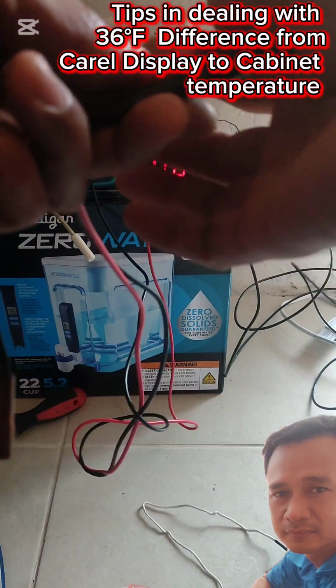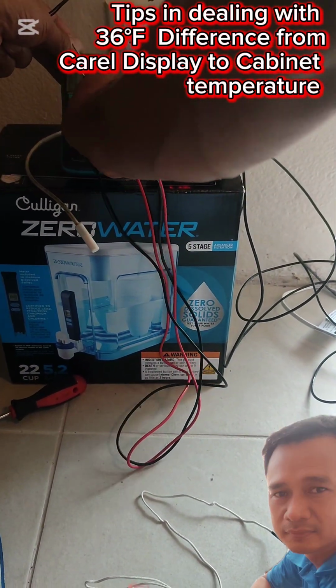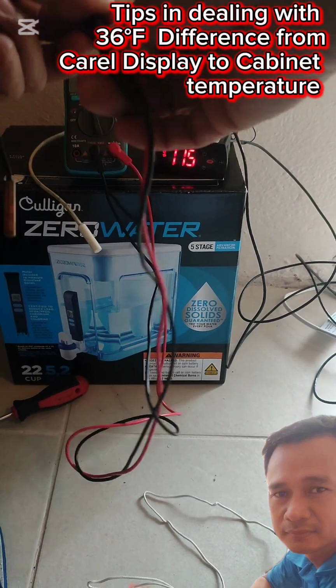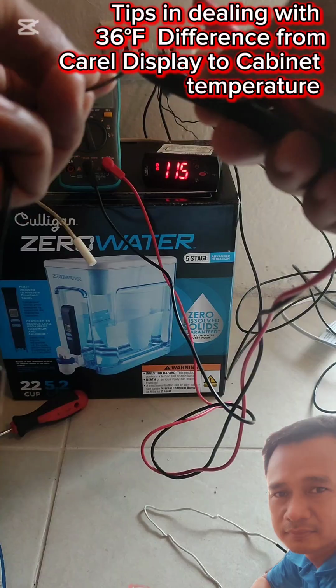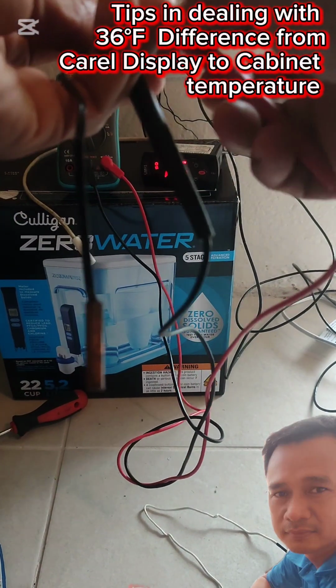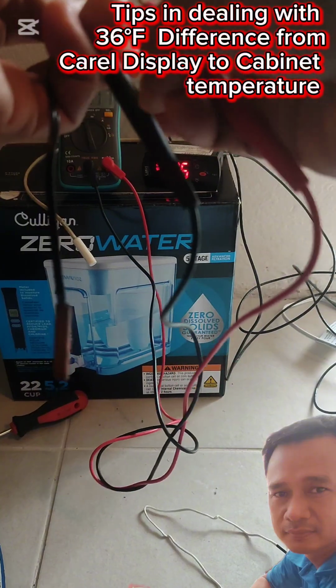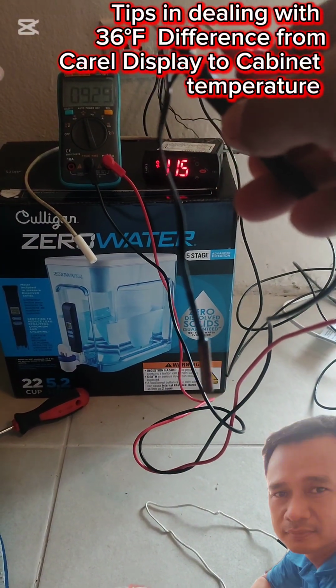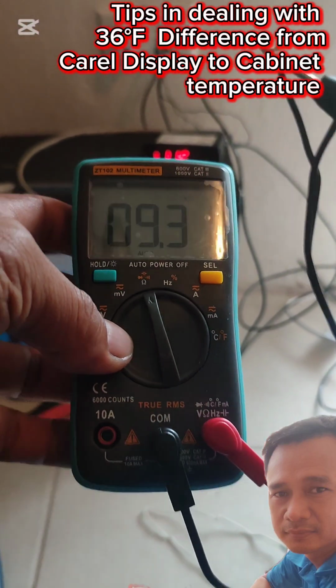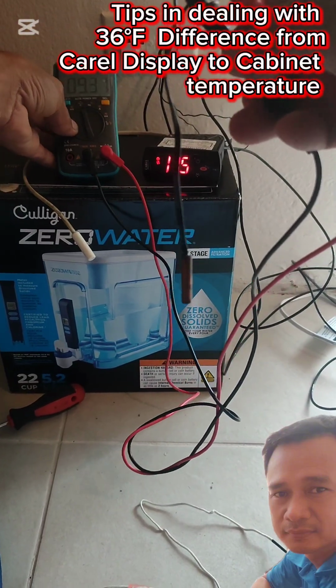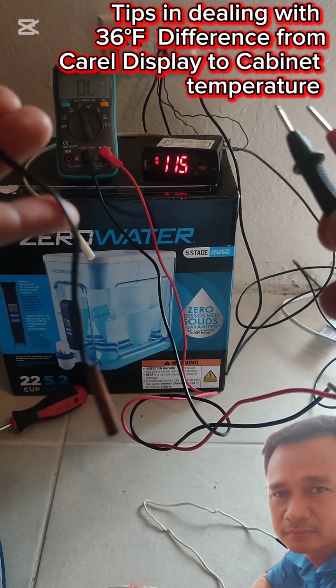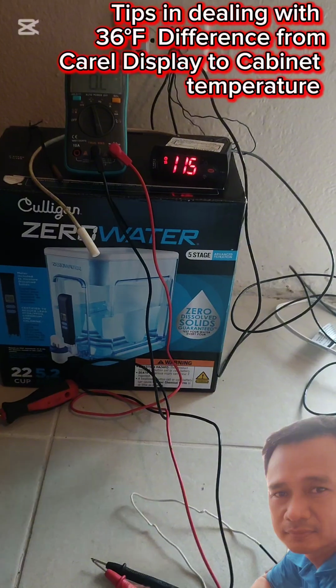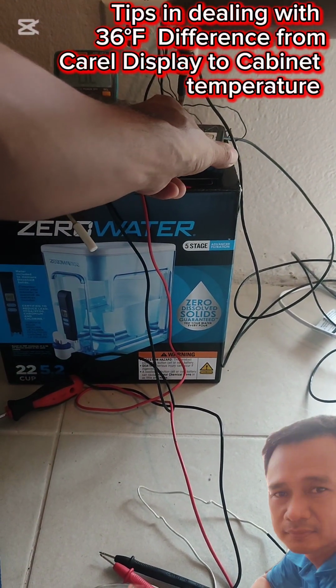Alright, now take a look, guys. I'm going to change this into resistance reading, and I'm going to measure this sensor, the pipe sensor of the air conditioning, and I got a reading of 9.29 or 9.30 kilo ohms. So I keep on saying on my blog that the NTC sensor ranges from 7 to 10 kilo ohms.